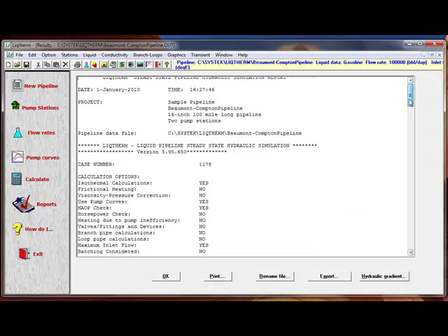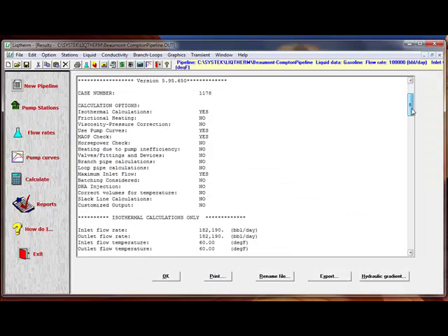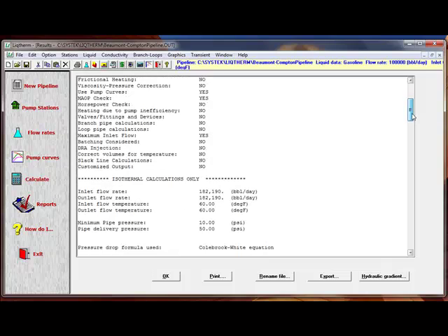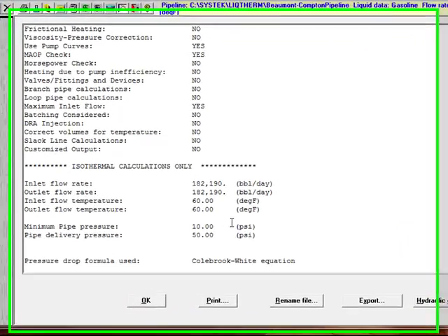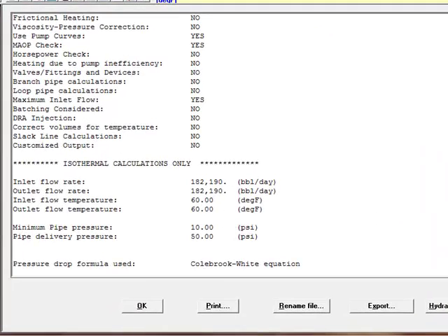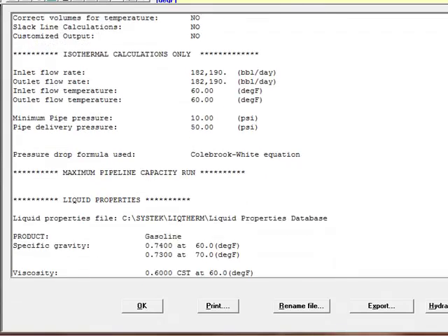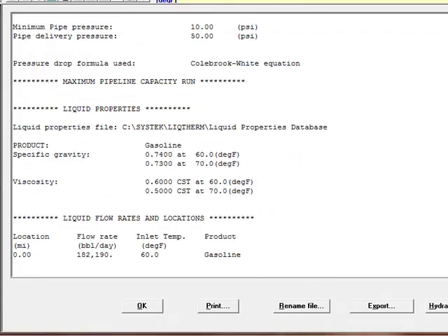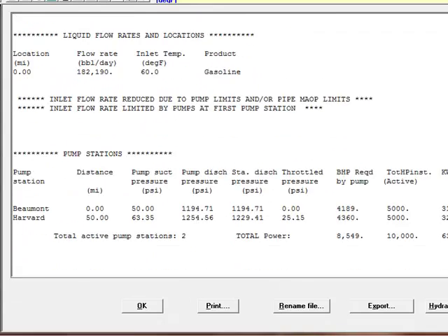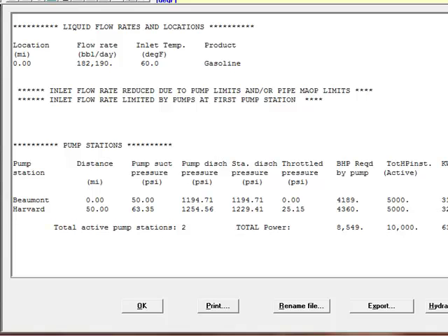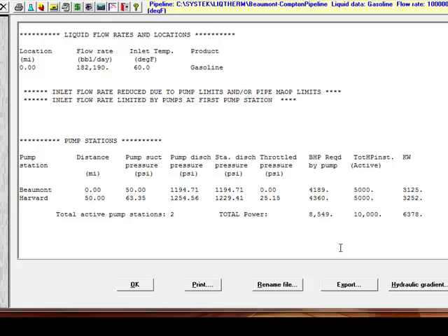This time the flow rate has been calculated at 182,190 barrels per day. And that is for considering gasoline as a pump fluid. And the horsepower required at the two stations are 4,189 and 4,360 or a total of 8,549.